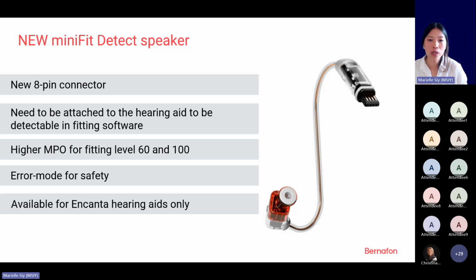The new receiver also includes an error mode, which is a safety function. So if you put the wrong fitting level or the wrong side by mistake on another Encanta, then the Encanta hearing aid will not give any sound, and you will also see that the LED will start giving long orange blinks with a total of 16 orange blinks. So that tells you there's something wrong with the speaker attached. Of course, the new miniFIT Detect speakers are only compatible with Encanta hearing aids. So please don't mix the older miniFIT speakers and the new miniFIT Detect, okay?